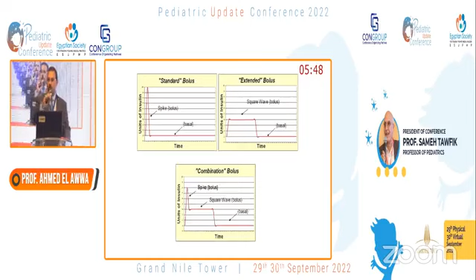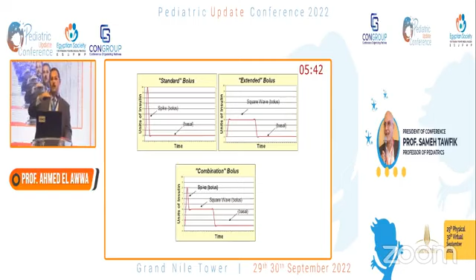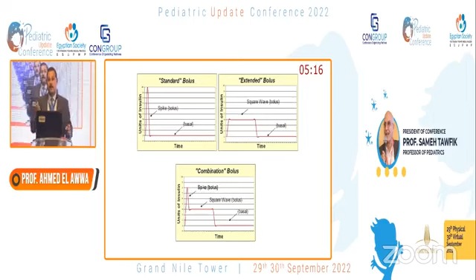Some advanced features as well for the bolus. The pump can give you the regular bolus, the spike one bolus, or it can extend the same dose of bolus over 1 or 2 or 3 hours, depending on the decision you are making, if this bolus is going to be consumed evenly over 2 hours, or there is a case of gastroparesis, or it can be dual. A bolus can be delivered now, and the rest is going to be extended over the coming 2 or 3 hours, and this decision is mainly for fatty meals. So you cannot do this with the pen.